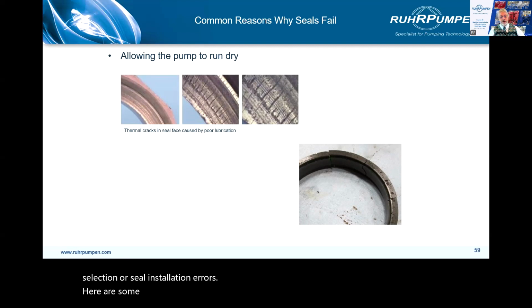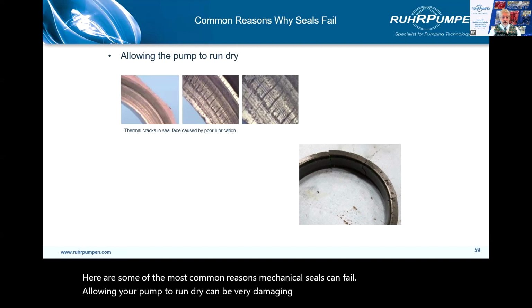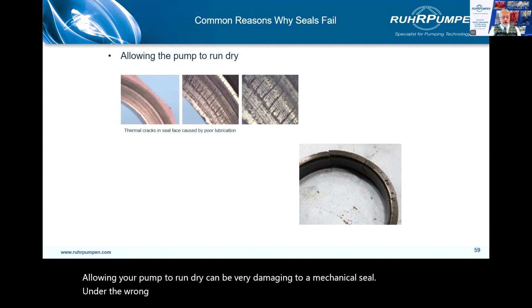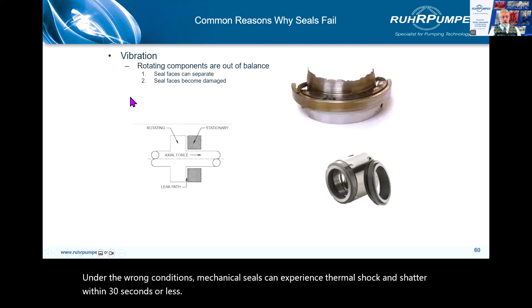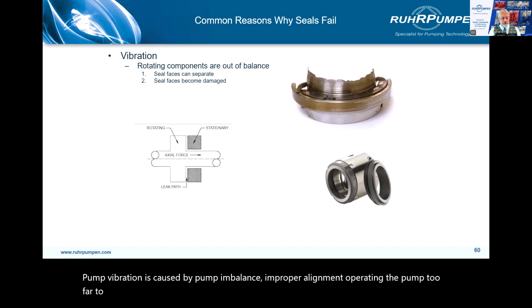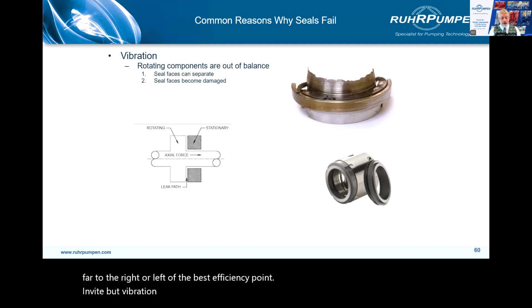Here are some of the most common reasons mechanical seals can fail. Allowing your pump to run dry can be very damaging to a mechanical seal. Under the wrong conditions, mechanical seals can experience thermal shock and shatter within 30 seconds or less. Vibration. Pump vibration is caused by pump imbalance, improper alignment, operating the pump too far to the right or left of the best efficiency point.